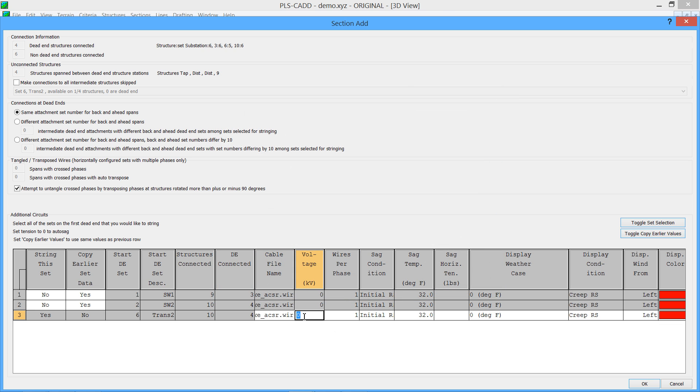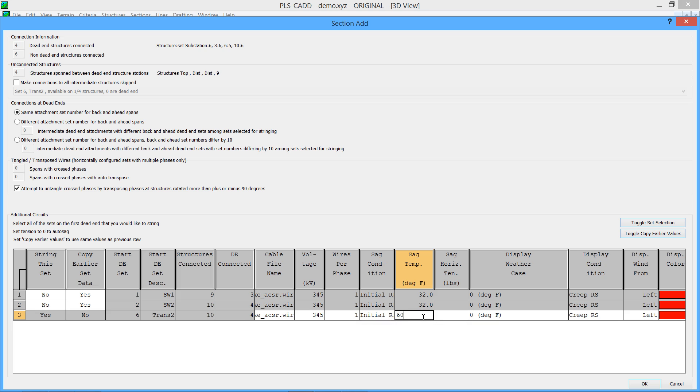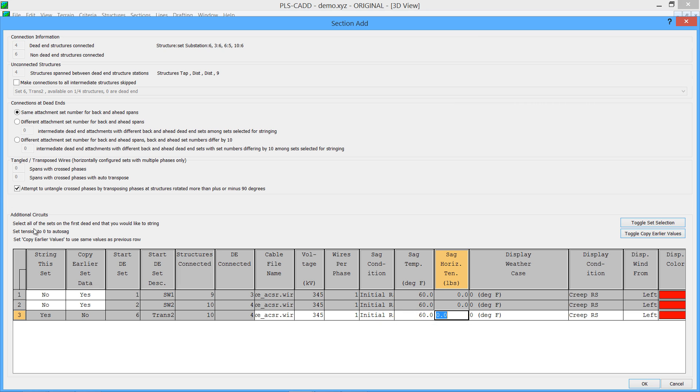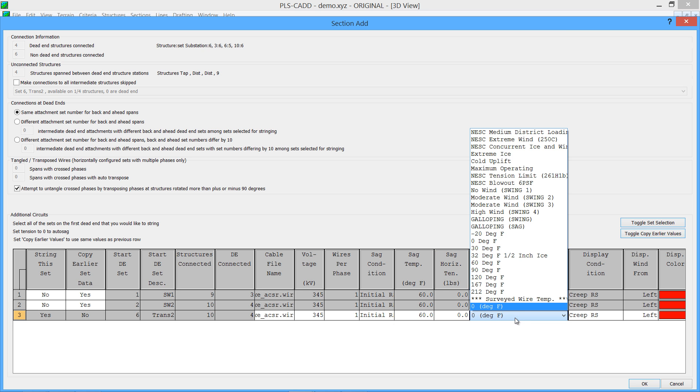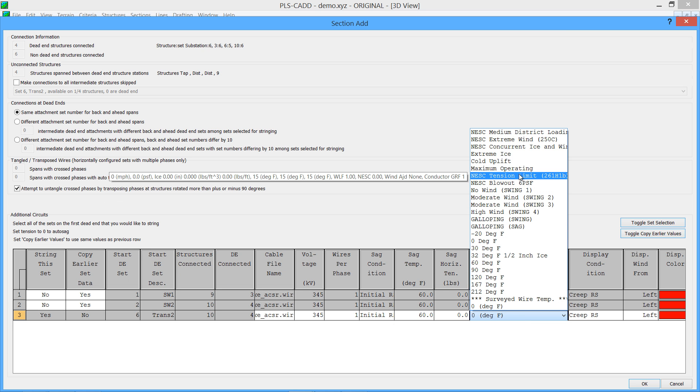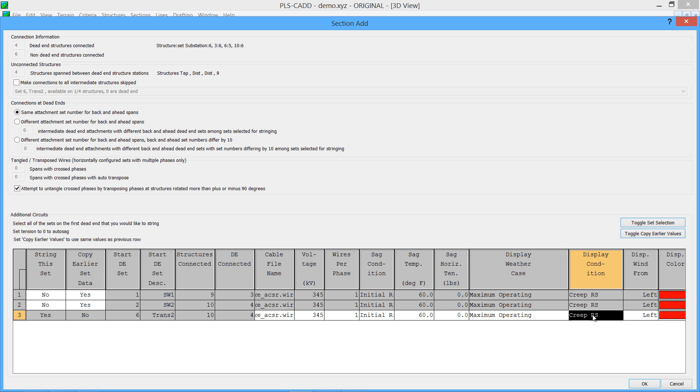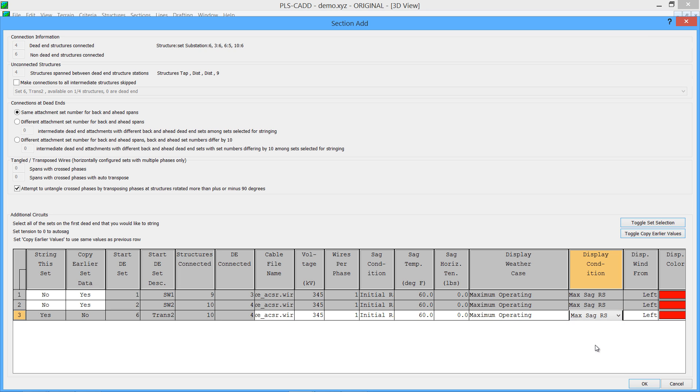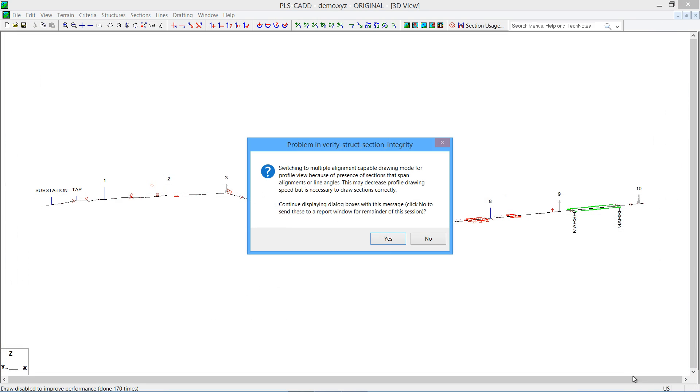So for this example, I'm just going to choose a default Drake ACSR conductor. Let's choose a voltage of 345, wires per phase of 1. Initial, let's make an assumption, is 60 degrees average temperature for the stringing. The horizontal tension, if you leave it on zero, it will automatically sag it. You'll notice up here in the information bar it says set tension to zero to auto sag. So unless you know the tension, just leave that on zero. You probably want to display the wire underneath the maximum operating condition, maximum sag, since we don't know which case is going to control the sag. All the other wires will match that, so you don't have to fill out each one of those sections of wires. I'm going to go ahead and click OK here.